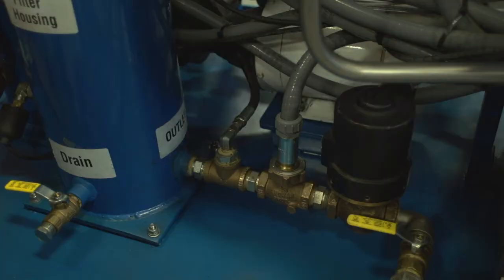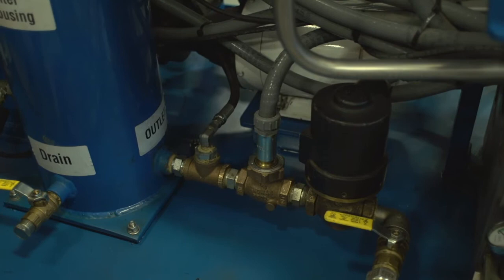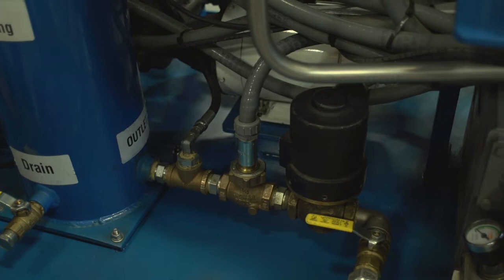A key feature of the DesCase HiVac system designed for transformer oil is the positive shutoff solenoid valves. These are electrically activated solenoid valves rated at 300 PSI differential. These valves are located at both the inlet and the outlet of the system and they positively isolate the vacuum dehydration degasification system from the transformer when the machine is turned off.